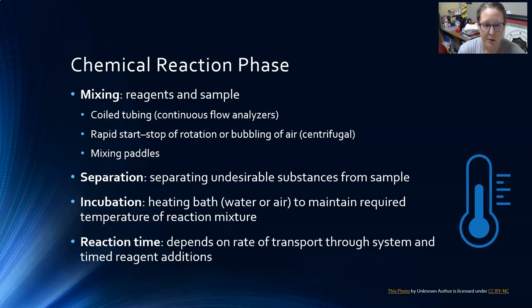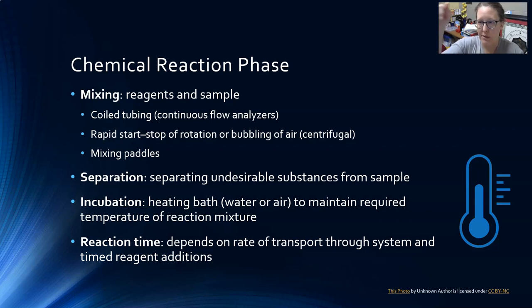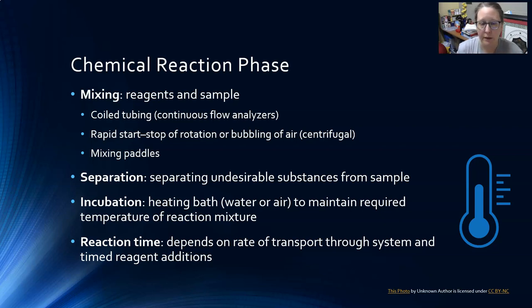In centrifugal analyzers, the rapid start and stop of rotation of a carousel shimmies and shakes to mix. You can also use bubbling of air to mix reagents, or mixing paddles — a little paddle that whirls and mixes the reagent and sample, cleaned between different reactions. If there is a need for a separation phase, as in some immunoassays, the system may use magnetic beads or similar methods to pull the parts that need to be analyzed.